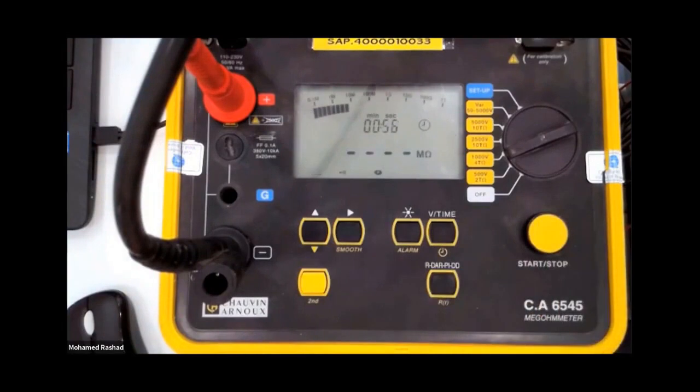So of course, after a minute, it will stop its injection all at once and will ask you how your equipment is doing. And it will tell you, of course, my CT is new and I have it here, but it hasn't been exposed to any stress or anything at all. So you will always find that even the insulation resistance is excellent without any problems at all.